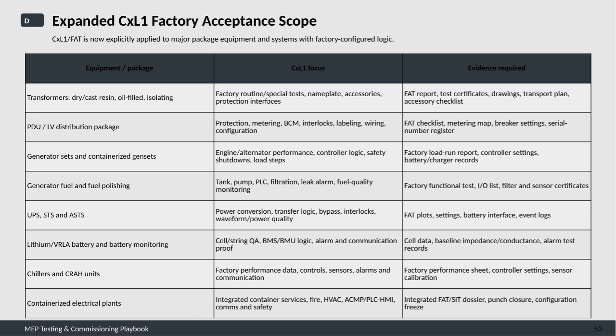In the case of power distribution units and low-voltage distribution packages, testing centers on protection functions, metering accuracy, building management communication, interlocks, labeling, wiring, and configuration. Required documents include FAT checklists, metering maps, breaker settings, and a serial number register. Generator sets and containerized gensets undergo tests on engine and alternator performance, controller logic, safety shutdown sequences, and load step behavior. The factory load run report, controller settings, and battery and charger records serve as proof.